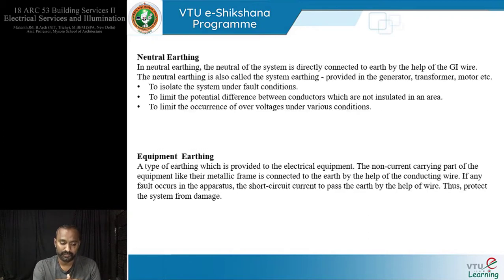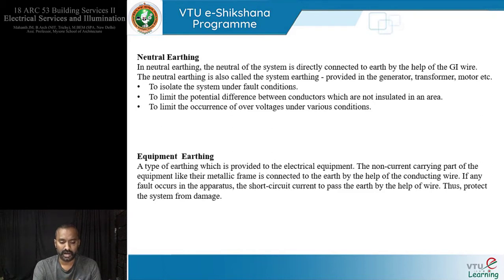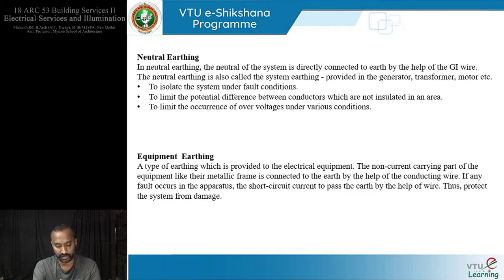There are two types of earthing: neutral earthing and equipment earthing. In neutral earthing, the neutral of the system is directly connected to the earth with a wire — this is also called system earthing, provided in generator and transformer applications. The idea is to isolate the system under fault conditions, limit the potential difference between uninsulated conductors, and limit the occurrence of overvoltages. Equipment earthing connects the non-current-carrying metallic frame of equipment to earth, so that any fault current passes to earth via the wire, protecting the system from damage.